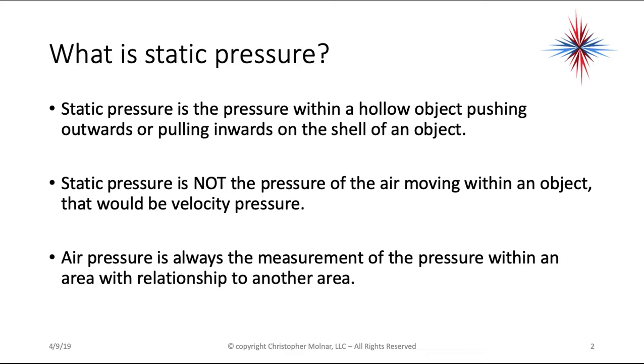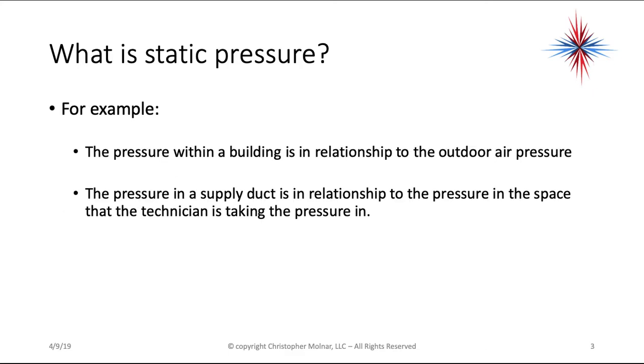Static pressure is NOT the pressure of the air moving within an object — that would be velocity pressure. Air pressure is always a measurement of the pressure within an area with relationship to another area. For example, the pressure within a building is the relationship to the outdoor air pressure. The pressure in a supply duct is in relationship to the pressure in the space that the technician is taking the pressure in. It's always a comparison of one area of pressure to another.